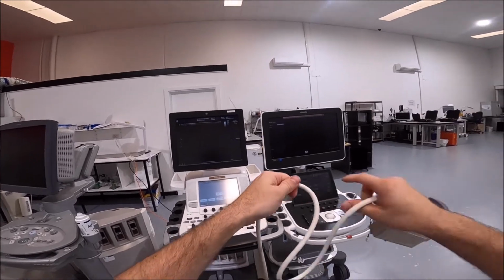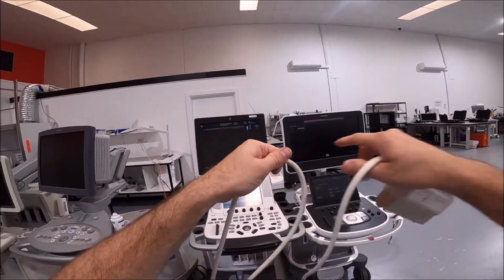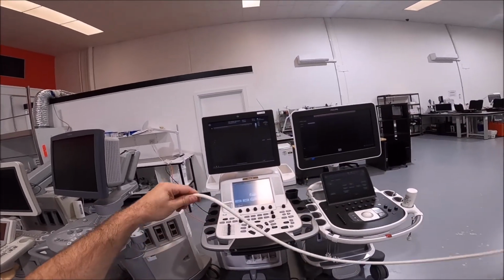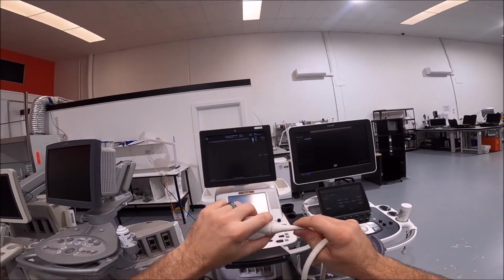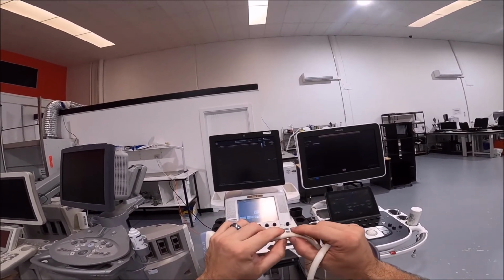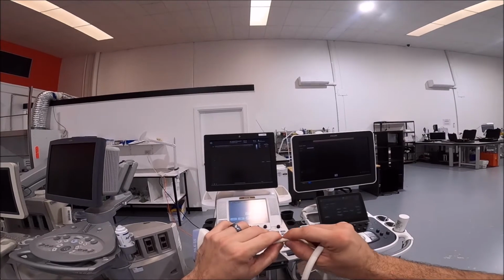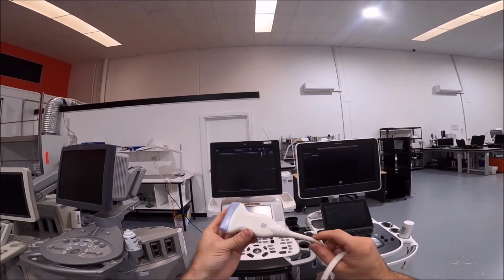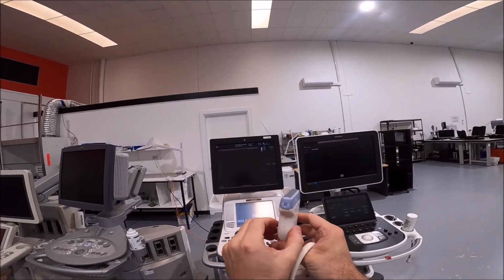Run your hand down the cable, check for signs of damage. Check the other strain relief. If strain reliefs are broken, it can result in inner cables breaking because it will only bend here, and that will cost you thousands. Check the cases on the probe.